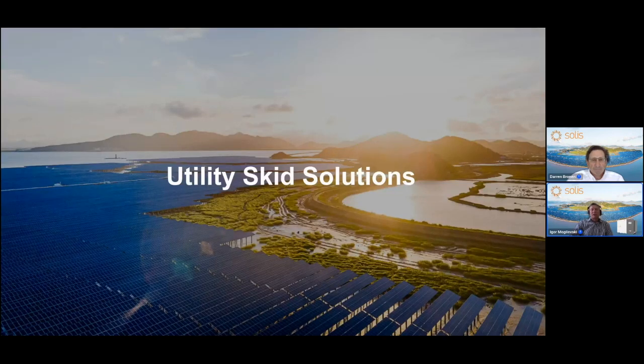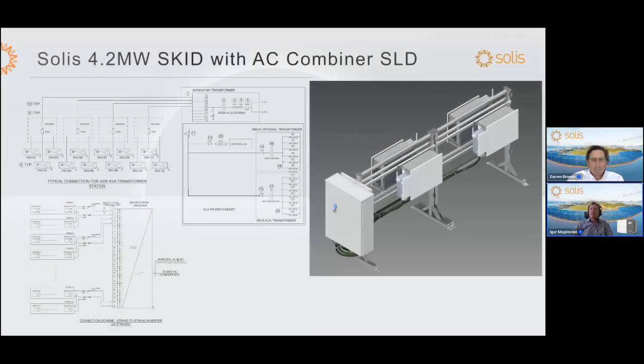So with this AC combiner and inverter, we also provide a skidded solution. We provide the skid, 4.2 megawatt here, shown as a sample of how a 4.2 megawatt skid could be connected as a single line. So we have 12 350 kilowatt inverters connected together with 3 inverters per AC combiner, and then 4 AC combiners connected to a low voltage bus bar in a medium voltage station. You have surge protection on the low voltage side and fuse protection on the medium voltage side.